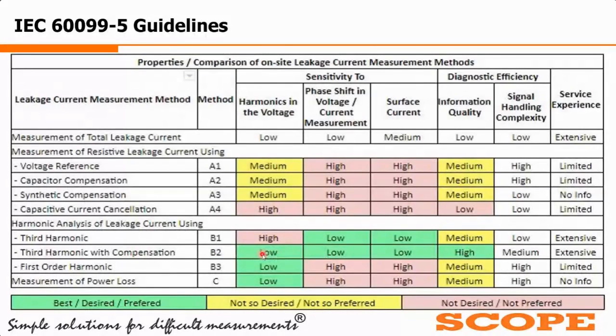So that's the reason people are talking about IEC 60099-5 method B2 as the most preferred way of measurement, followed by this one, B1. There, only the third harmonic measurement is preferred, and that's the reason we are talking today about the third harmonic measurement. Other methods are used, but they are not that much preferred or not that much popular.